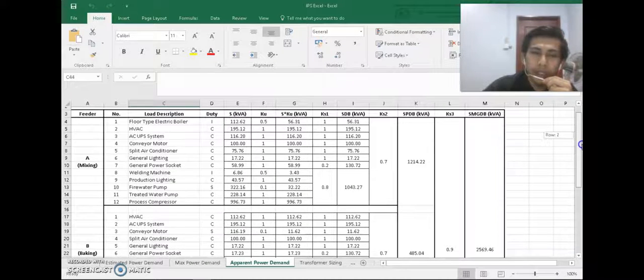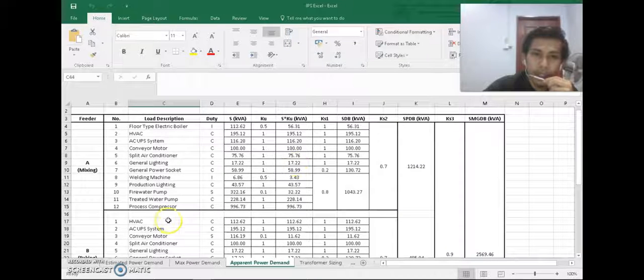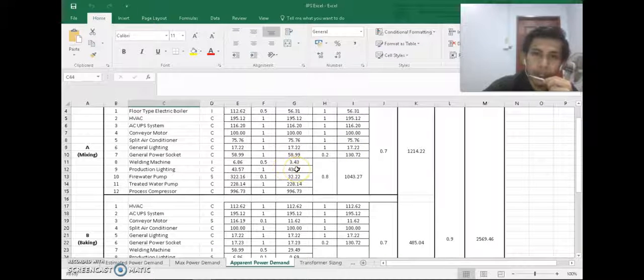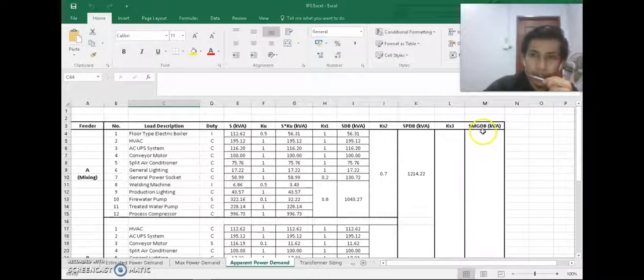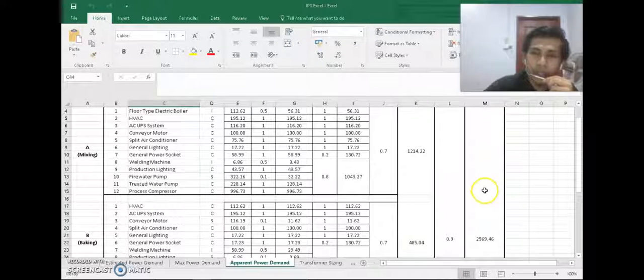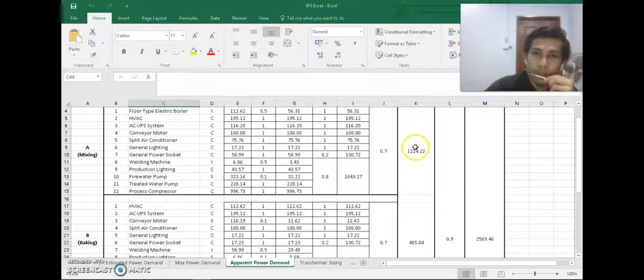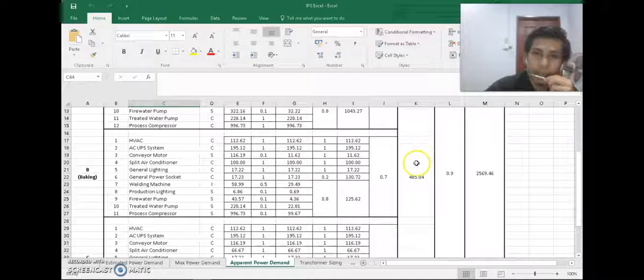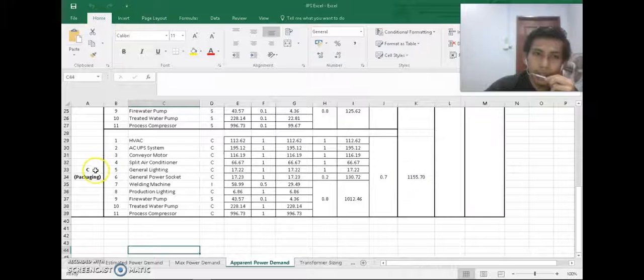Okay, after we finish this Excel for apparent power demand, we can create a circuit on the ETAP based on this. This is for the upper transformer, the main transformer, and then this is for feeder 1: kVA for feeder A, kVA for feeder B, and kVA for feeder C.